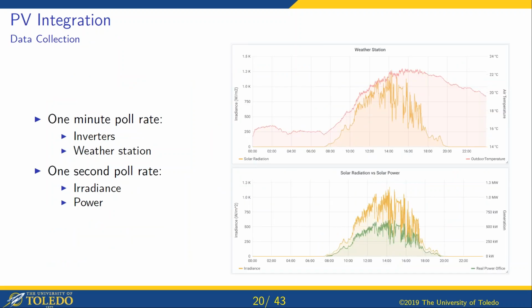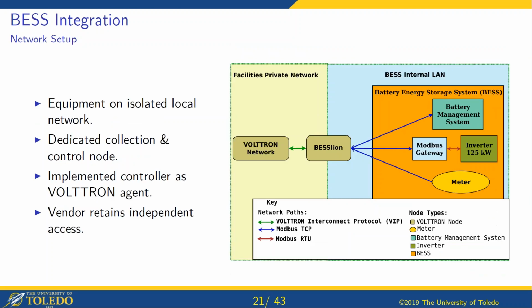We're already getting the energy, and we are actually pulling a lot of that data. The important stuff we're pulling once per second. When we're looking at the PV array, we're very interested in rapid changes in power, so for irradiance and power readings we're taking those very fast. Things like temperature and state of the inverters we're pulling less frequently, more like the buildings.